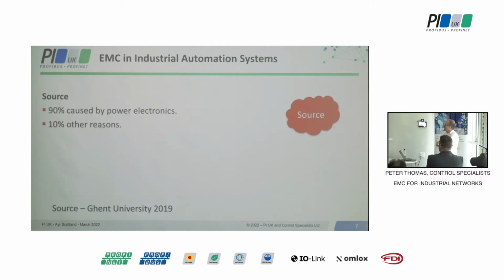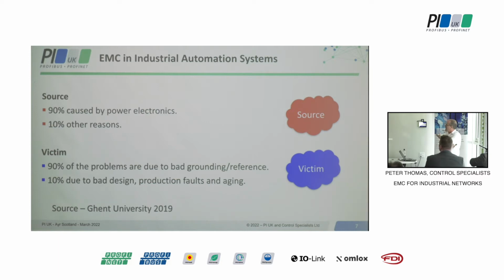This was a brief and useful slide given by a guy who came to one of the PI conferences from Ghent University. Based on their analysis in industrial automation, in terms of sources, 90% of EMC issues are caused by power electronics and switching devices, 10% by other aspects. In terms of the victim, 90% of problems are caused by bad grounding or reference. Now, I'm going to take issue with that word grounding, as we'll see shortly. But fundamentally, these are the biggest issues they're seeing, and I can vouch for that from my own experience.